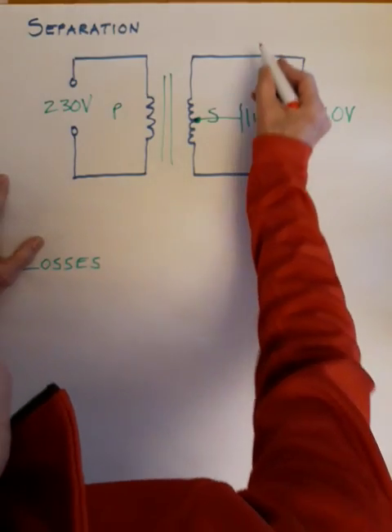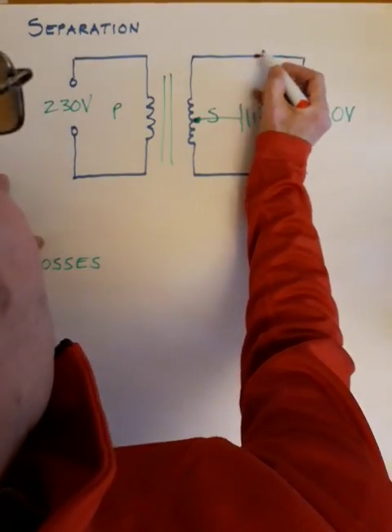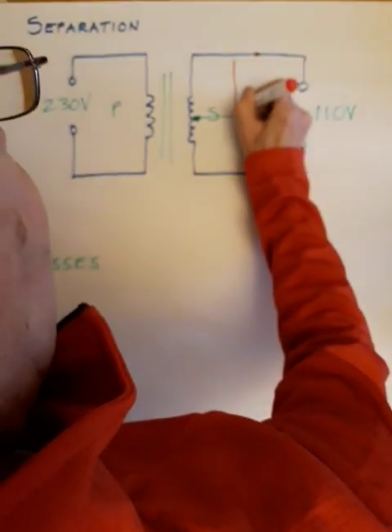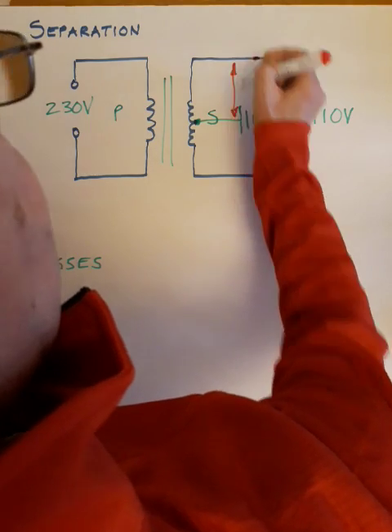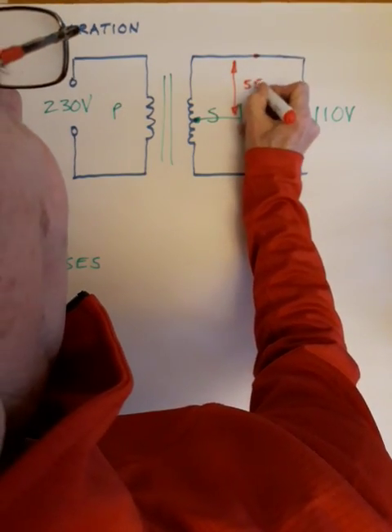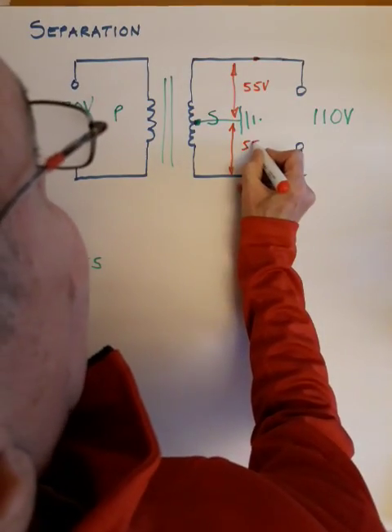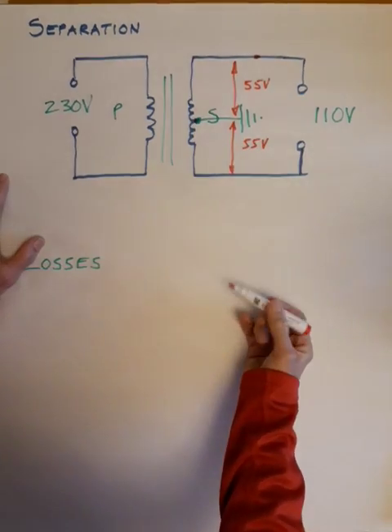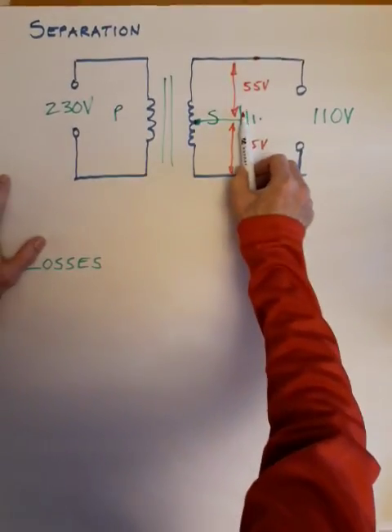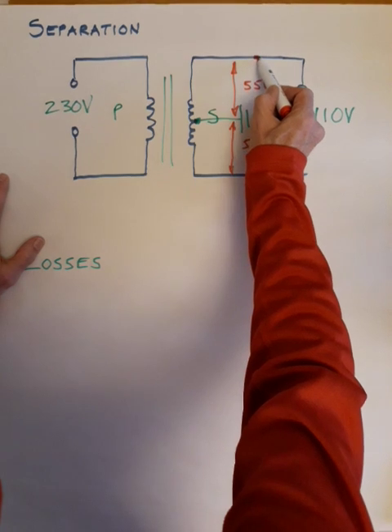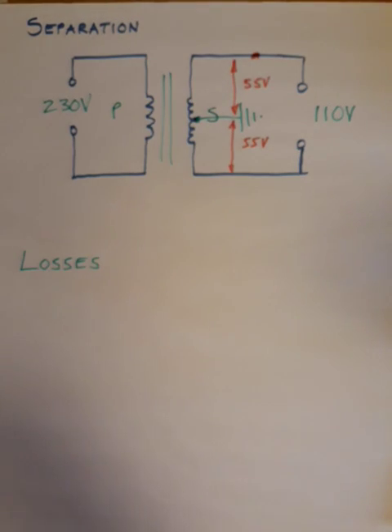That's again a safety feature for people working on site. If you were unlucky enough to touch this, you won't get a 110 volt shock, because from earth to here is only 55 volts, and from earth to there is 55 volts. So in short, those two add up to 110, which is what we get out. But if you're unlucky enough to come into contact with this live line, you'll only get a 55 volt shock, so you have a much reduced chance of it killing you. I've never heard of 55 volts killing anyone.